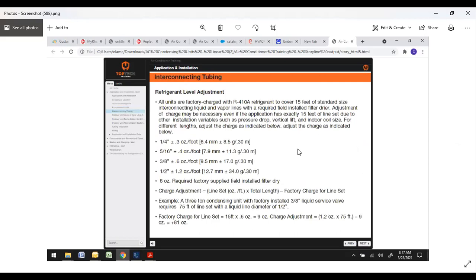Refrigerant level adjustments. All units are factory charged with 410A to cover 15 feet of standard size interconnecting liquid and vapor lines with a required filter dryer. Just because it says 15 doesn't necessarily mean you won't have to add any. Adjustment of charge may be necessary, even if the application has 15 feet of line set, due to other installation variables such as pressure drop, vertical lift, and/or coil size. So for different lengths, adjust the charge as indicated below.